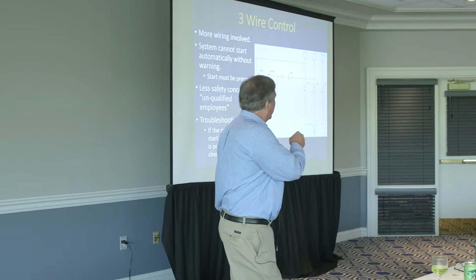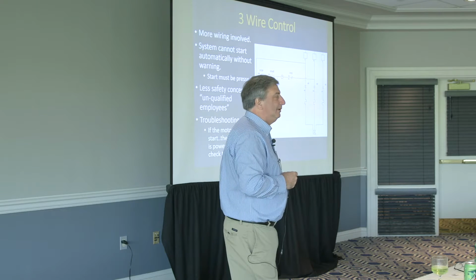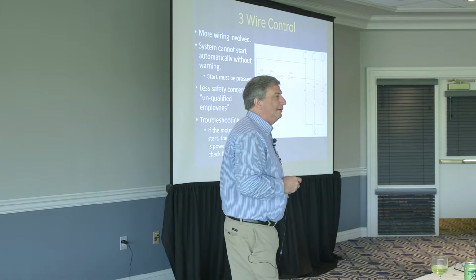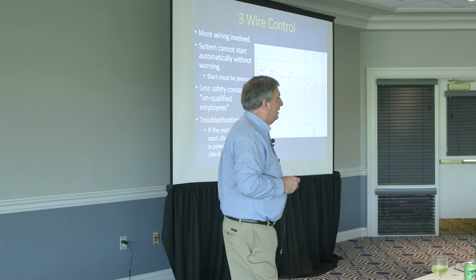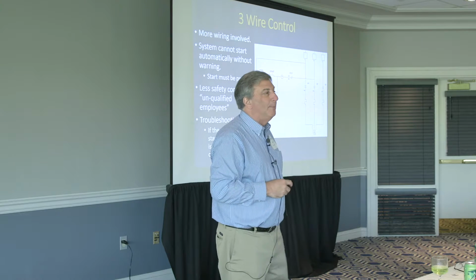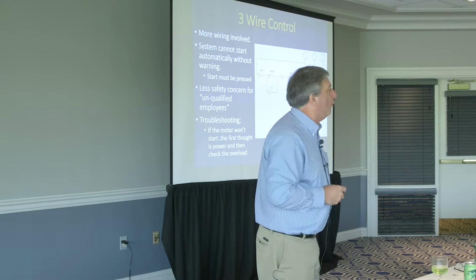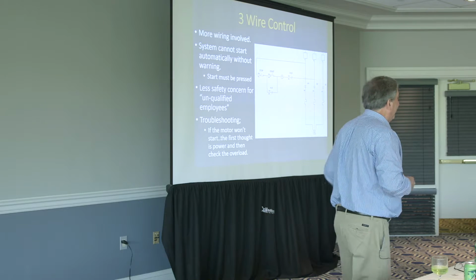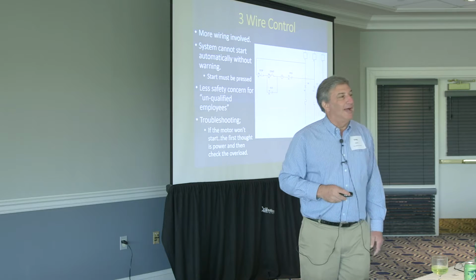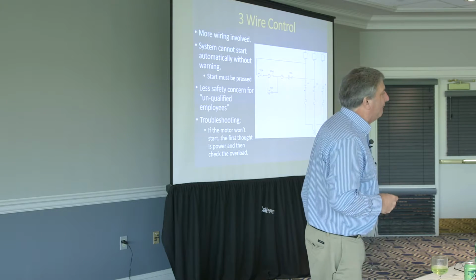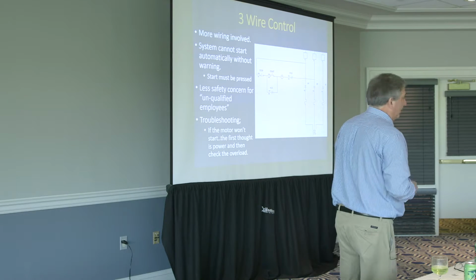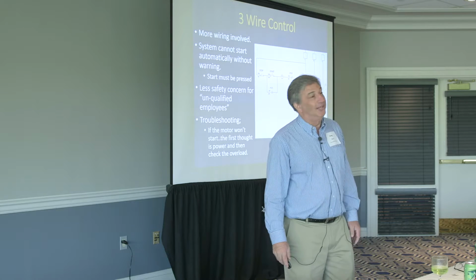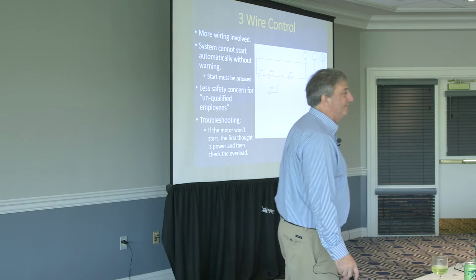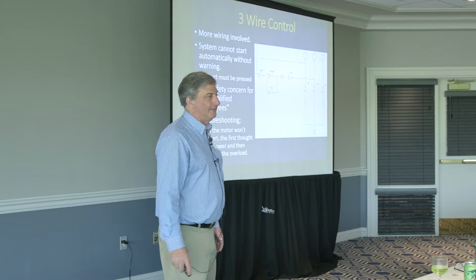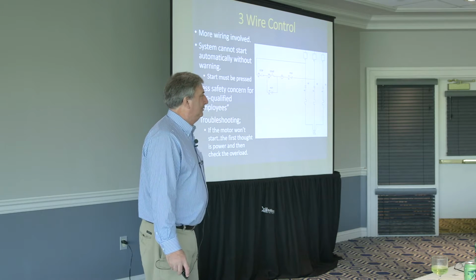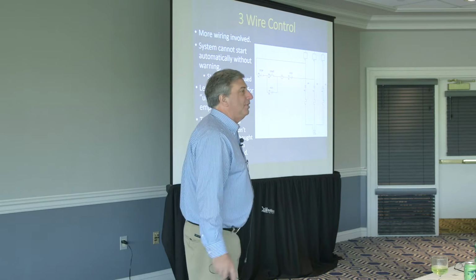What if the power went off? So the power had a little blink. And now what do I have to do to go turn that pump back on? I have to walk out there and go to the button after the outage. And if I have 50 pumps I have to turn back on, pretty soon I'm saying, this is a load. I don't like this. We got to fix this. Okay? Well, there are ways to do that.